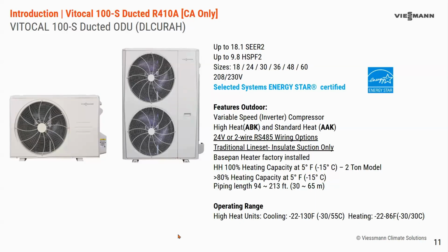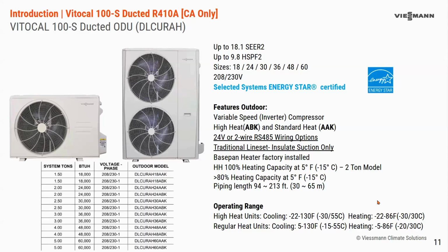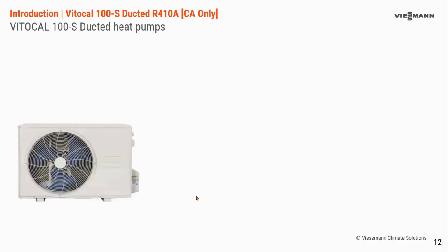From an operating range standpoint, the high heat is down to -30°C in both heating and cooling, and up to 130 degrees Fahrenheit, 55°C. The regular heat has a much milder operating range of -15 to 55 in cooling and, sorry, there's some conversion error there, but essentially -5 degrees on the heating side. Okay, I see. So it's 5 on cooling, -5 on heating. And there are your model numbers. They're just AAK, ABK high heat. Again, we have sizes 18 to 60,000 BTU, and these are all the ducted outdoor units.